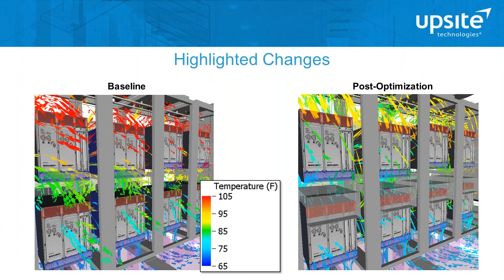Correct. So I suppose the pièce de résistance is the next slide, Lars, which is really the results. The airflow - we reduced it, switching off some fans or reducing fan flow rates. I'm not the person who did the work so I may stand corrected, but the bulk numbers are: total CFM supply went down from 722,000 to 541,000, and we managed to raise the chilled water temperature by 5 degrees Fahrenheit.